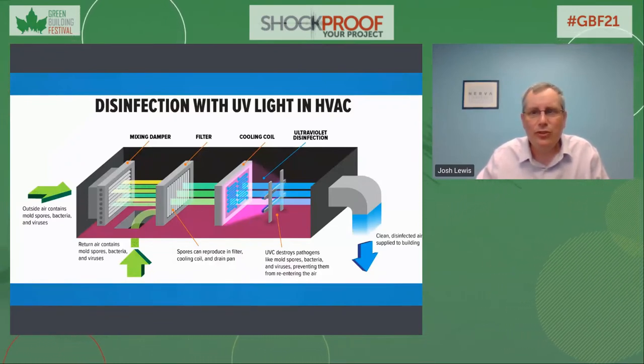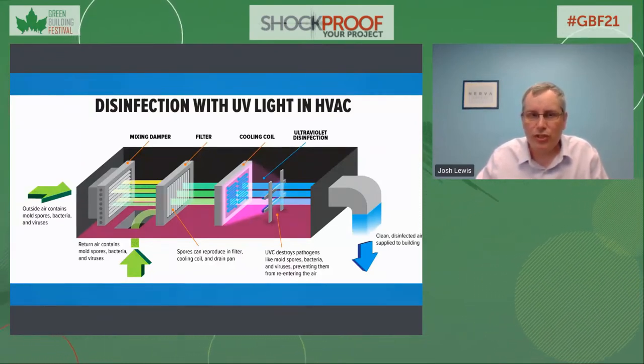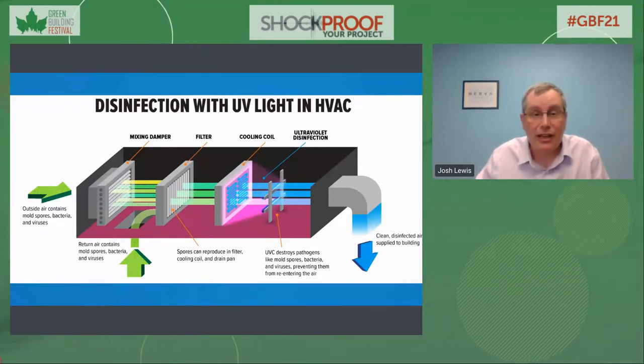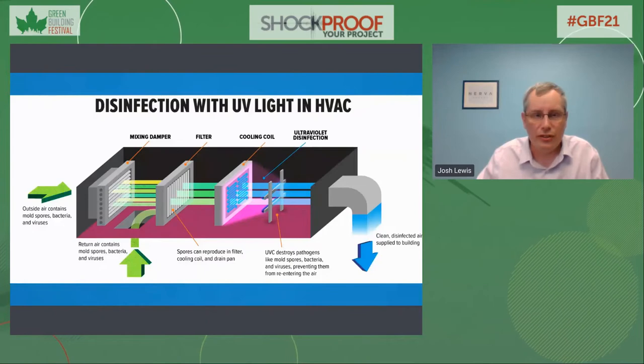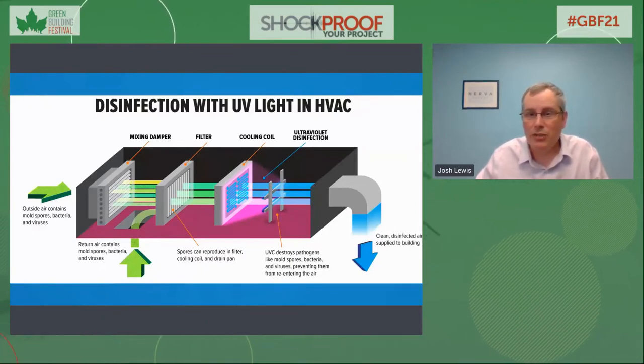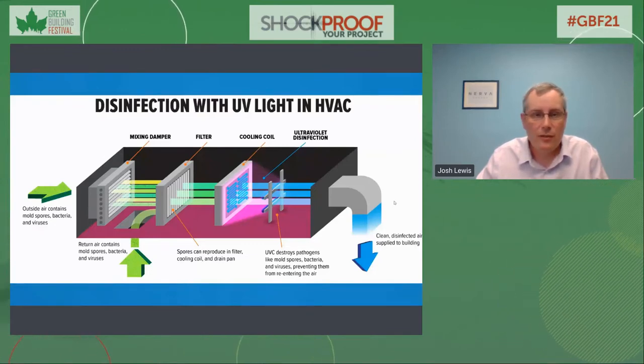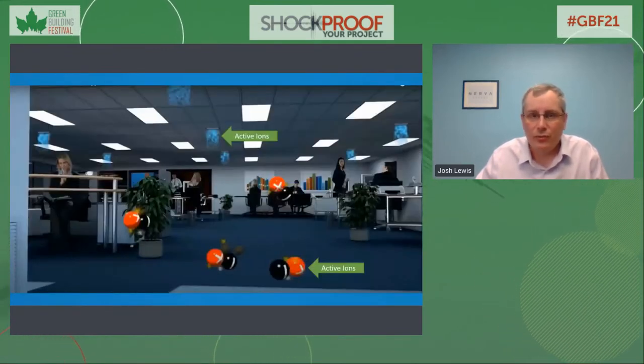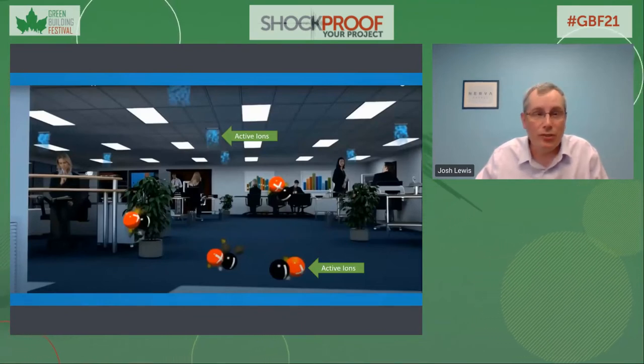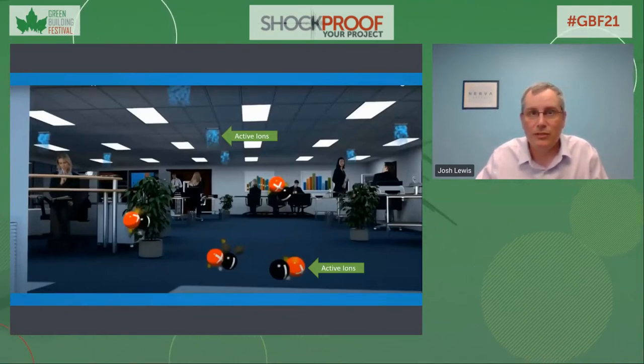They typically use UV light or an electrical discharge to drive a chemical reaction which can produce active ions within the airstream, such as hydroperoxide, ozone, and other types of ions which flow with the air into all areas serviced by the system, directly attacking contaminants through the surface space, both in the air and on surfaces. Active air purification, when implemented properly and safely, has major advantages over passive systems. They essentially fill the building with beneficial ions, turning the air itself into a protective blanket.